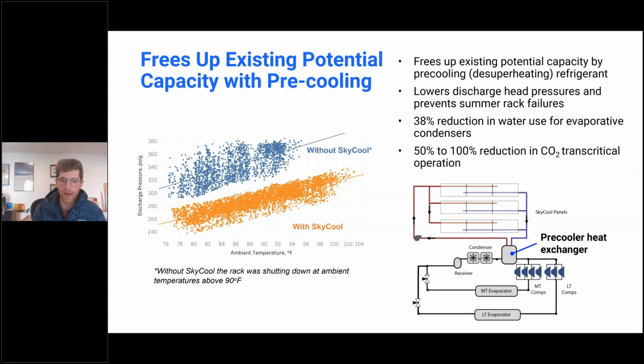In the case of evaporative condensers, it's a way to reduce water usage. And so I'll talk about a case study where we installed this with an evaporative condenser, and we're able to reduce water usage by about 40%. And then in CO2 refrigeration systems, so these are transcritical refrigeration cycles, we're able to reduce the number of hours where the system went transcritical in its operation.